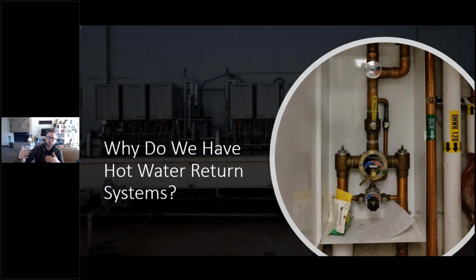So recirculating is the term I'm going to use for the circulation that's coming from the hot water source to the building, and that follows ASPE's latest Legionella design guide, which I would recommend getting a copy of if you haven't already. We defined recirculation as that process of bringing hot water from the hot water source to the plumbing fixtures and then back again. Circulation systems we defined as if you have a separate storage and boiler. So just to clarify some terminology, we have these hot water return systems to bring that hot water source as close as possible to the fixture it serves. And there are any number of requirements from there.